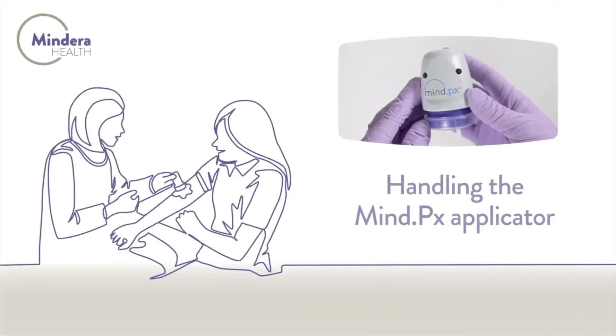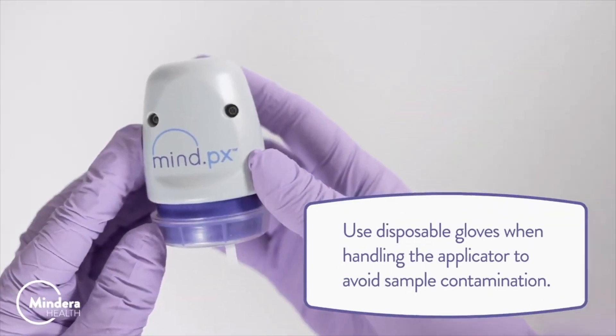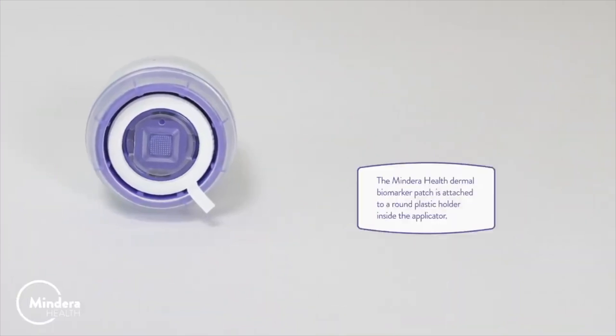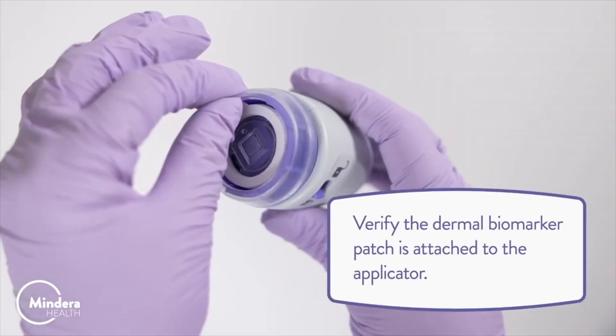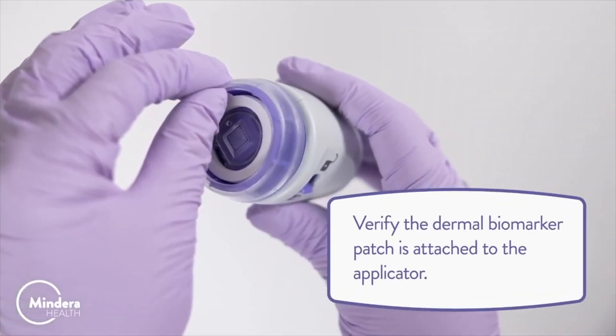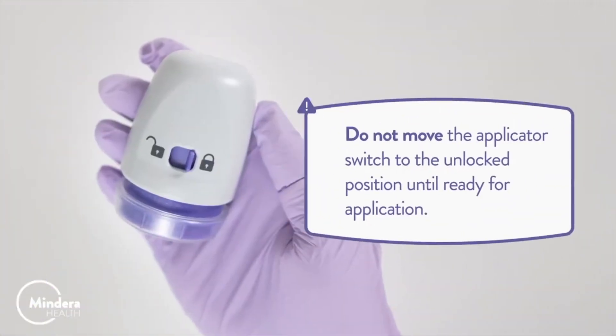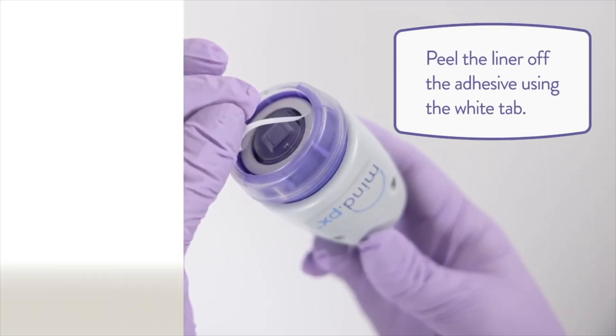Handling the Mind.Px applicator. Use disposable gloves when handling the applicator to avoid sample contamination. The Mindera Health Dermal Biomarker Patch is attached to a round plastic holder inside the applicator. Verify the Dermal Biomarker Patch is attached to the applicator. Warning: Do not move the applicator switch to the unlocked position until ready for application. Peel the liner off the adhesive using the white tab.